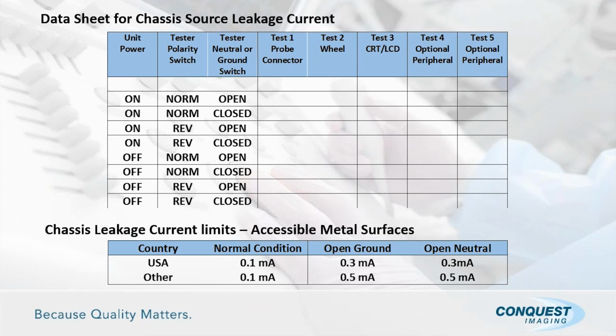So those are your limits. These are the chassis leakage limits. You can see they're slightly different from the USA to other countries. They again, in 2015, made this adjustment so that we're both at 0.5 milliamps now. So it's up to you how you want to interpret this. If you're using the OEM manual and it says 0.3, that's probably because the manual was written prior to 2015. But be aware that these are the current conditions. That was the current readings.